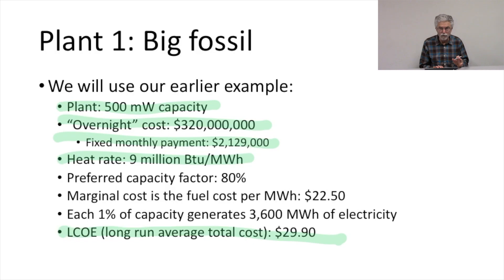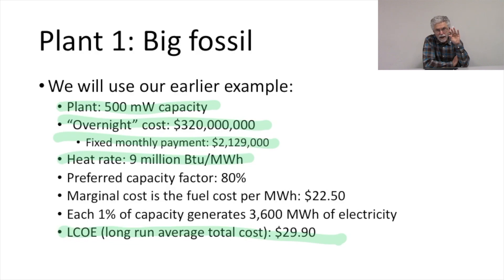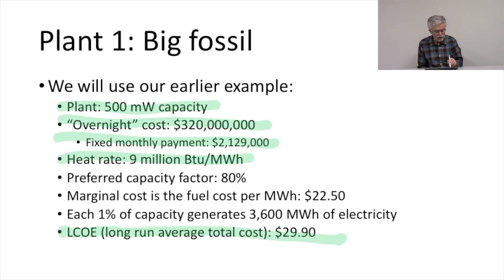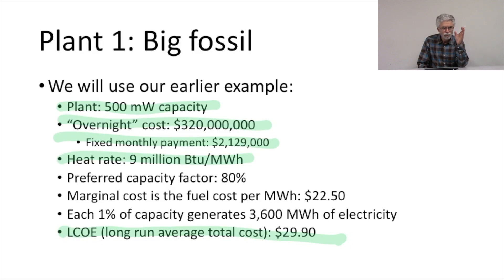This is a big base load power plant, and each 1% capacity will generate quite a lot of electricity. The long run average cost — the levelized cost of energy from this power plant — is $29.90. That is the average total cost of the power plant at the anticipated capacity factor. The levelized cost of energy is the long run average cost at the capacity factor we expect to have for this power plant — the average capacity factor over its lifetime.